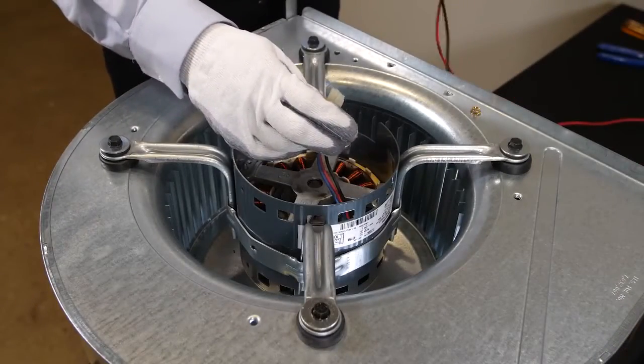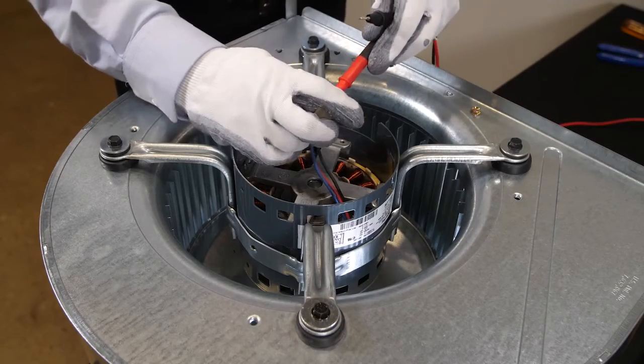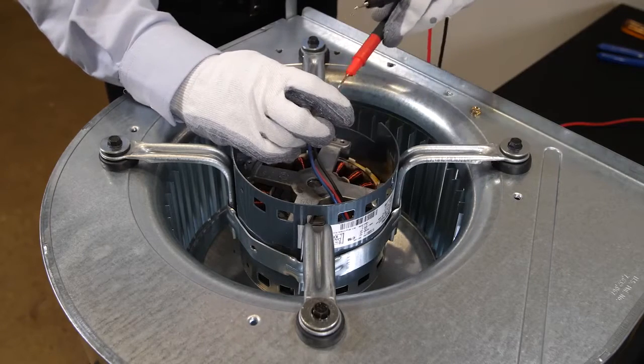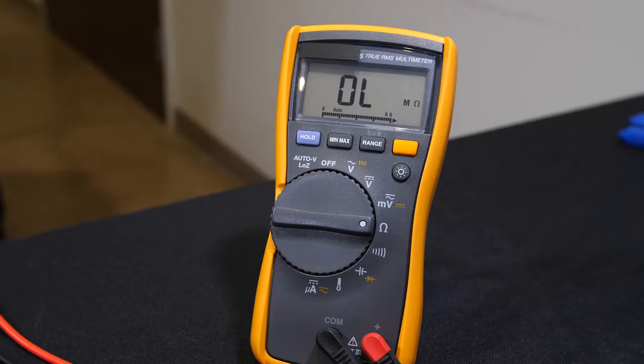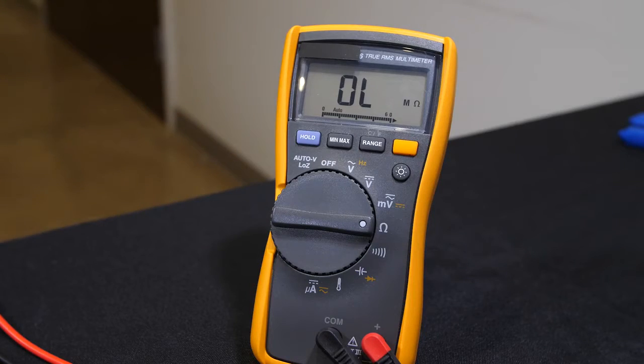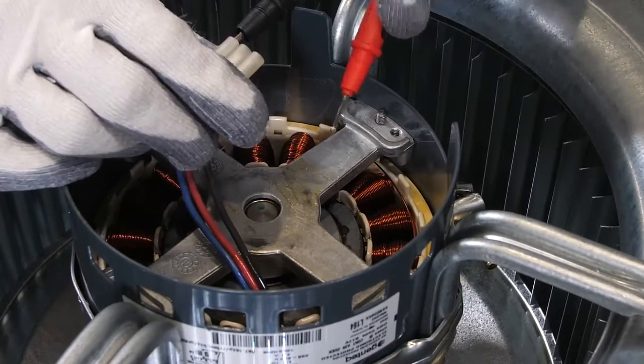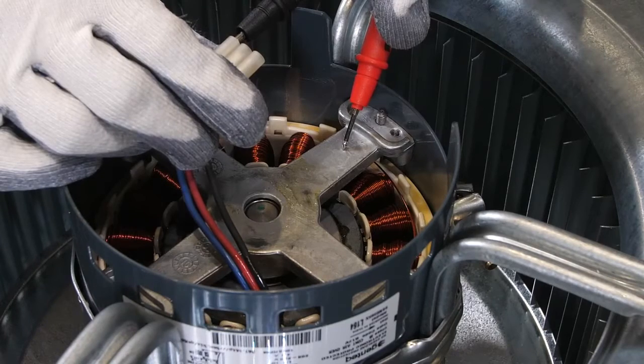Check for short to ground. Use an ohm meter to measure the resistance from all three of the motor connector pins to the aluminum end plate of the motor. This resistance should be greater than 100,000 ohms. If this test fails and you have less than 100,000 ohms, you have a defective motor and it needs to be replaced.